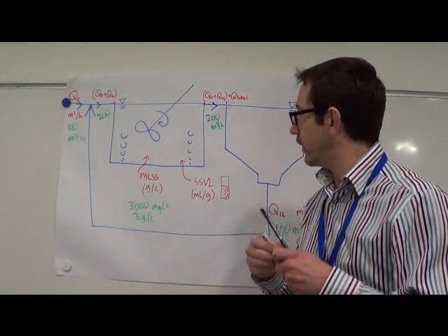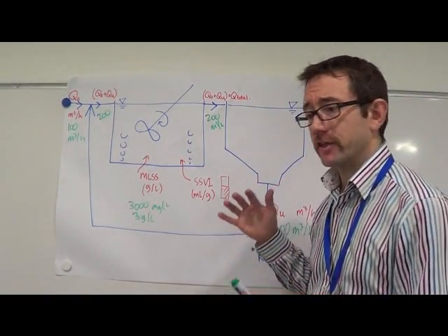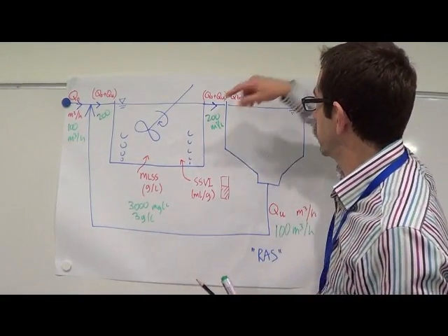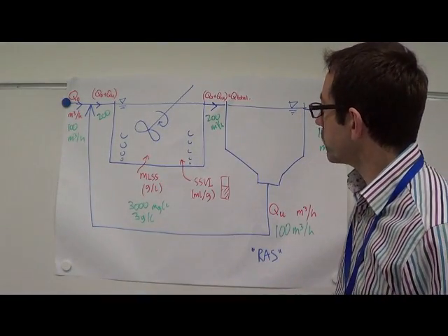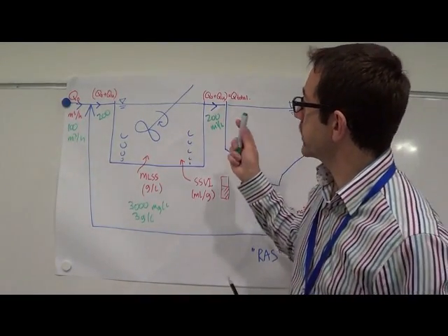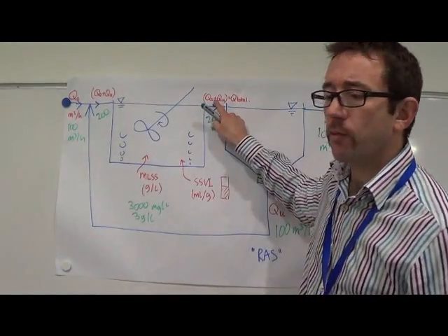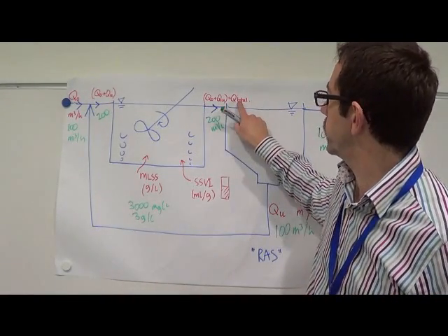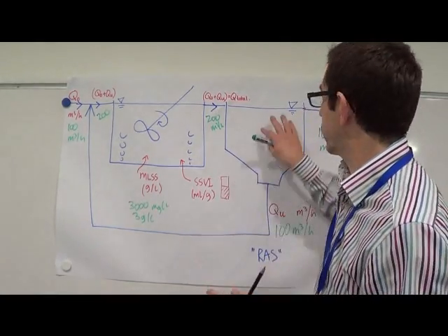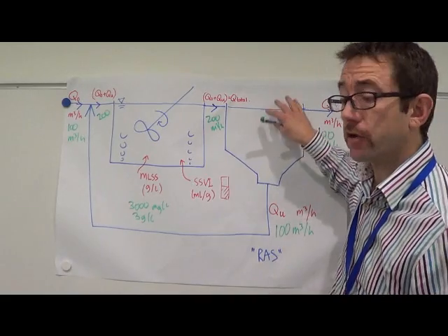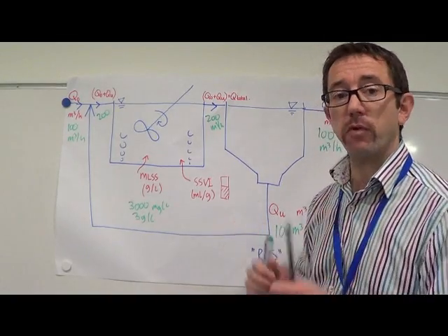And there you've got your loop. That's fairly important, and it's pretty key because what we're going to talk about in a minute is all about a bit of a mass balance around this stuff. So it's important to get our minds around that there's 200 of these things coming in, 100 going around the bottom, 100 going out the top. The only other thing to say is I've called those Q0 and QU, which you can see are 100 and 100, and the 200 we're going to use when we look at this chart in a minute, we call Q total. That's the total flow coming in and also the RAS going onto the final tank. That's going to be really important because that dictates how much solids you've got hitting that tank every hour. Okay, we'll pause it there.